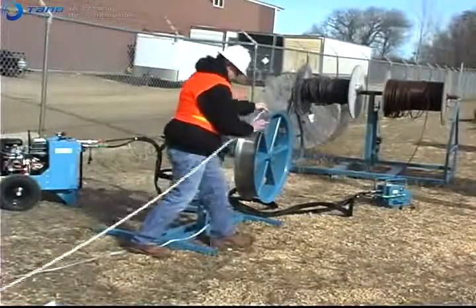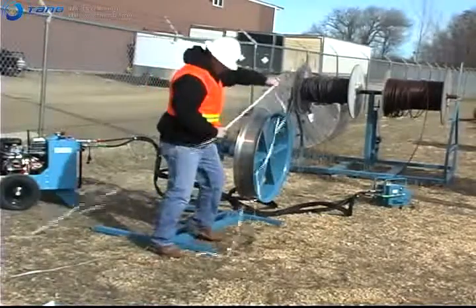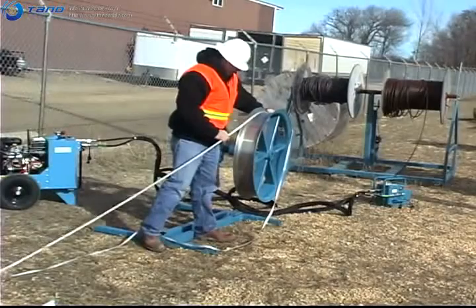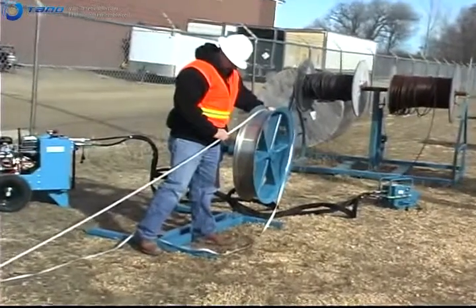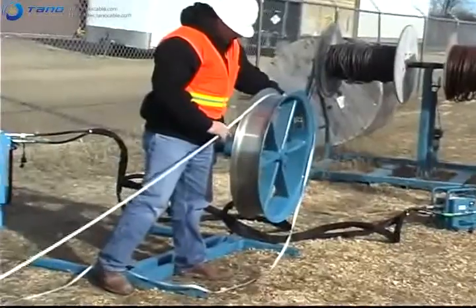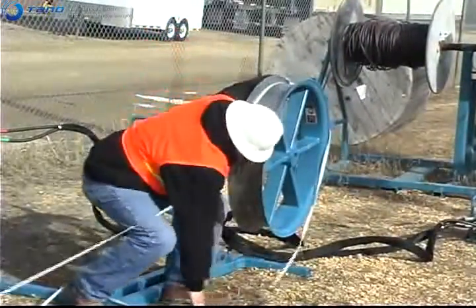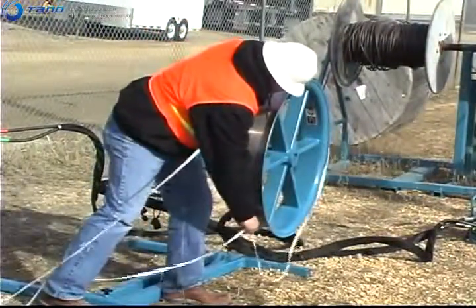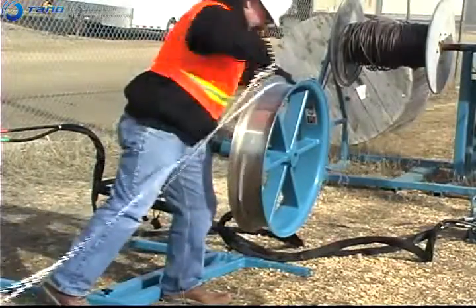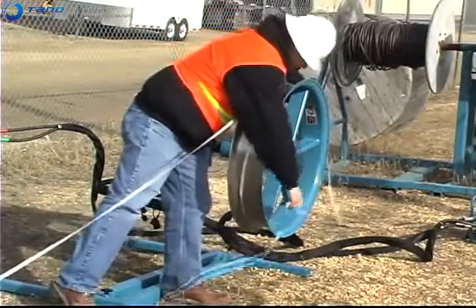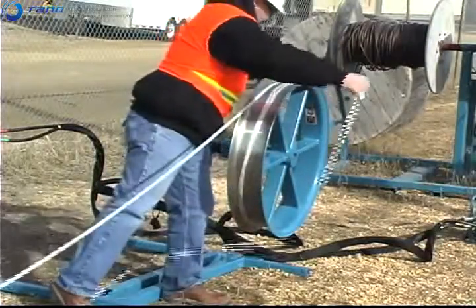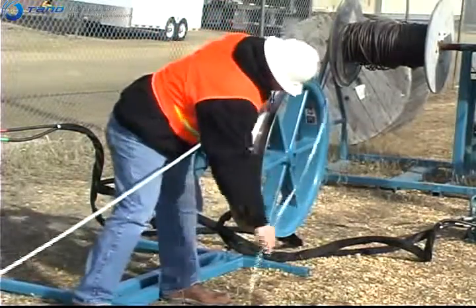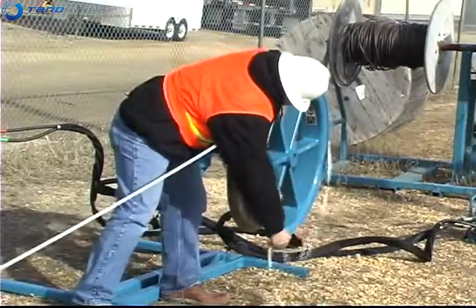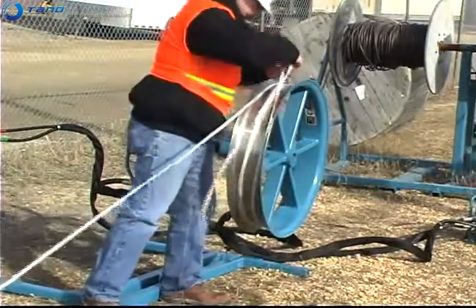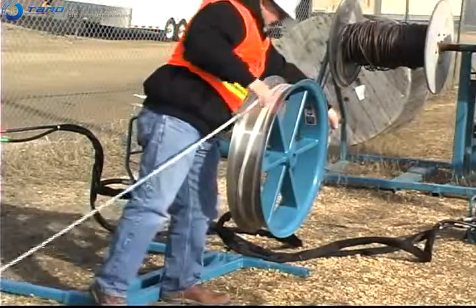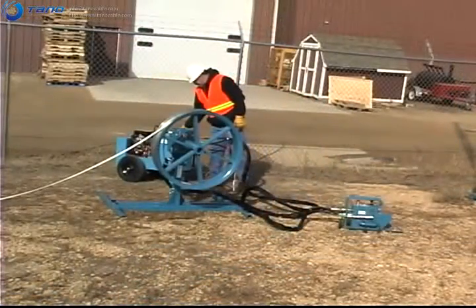The pull line will wrap best on the capstan if the capstan is angled about 10 degrees away from the pull line. This will allow the line to walk down the side of the capstan and push the previous wraps to the side. Place 4 or more side-by-side wraps of the pull tape around the capstan in the direction of rotation. Do not wrap more than 1 layer of pull line on the capstan. Start the hydraulic power source.